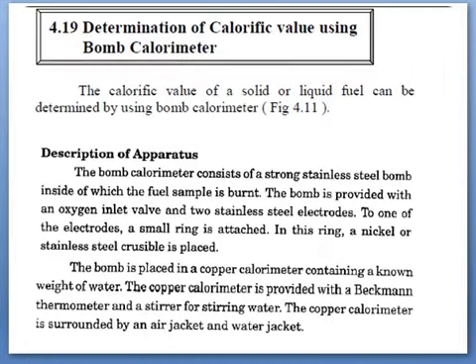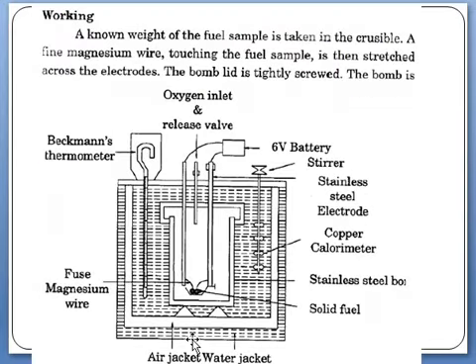The bomb is placed in a copper calorimeter containing a known weight of water — the entire stainless steel bomb assembly is placed inside the copper calorimeter filled with water. The calorimeter is provided with a Beckman thermometer and a stirrer for stirring the water. The copper calorimeter is surrounded by an air jacket and then a water jacket.